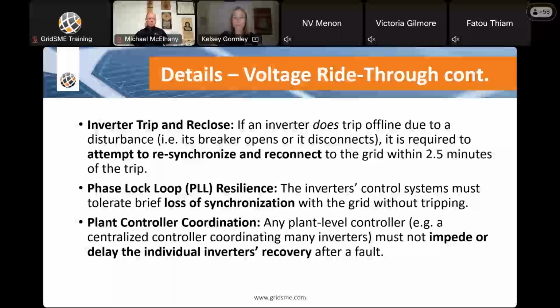Inverter control systems must tolerate a brief loss of synchronization with the grid without tripping. If the grid voltage phase reference is lost or slips, the inverter's PLL should freeze at the last known phase angle and continue injecting current at that phase for up to 150 milliseconds while the inverter attempts to relock to the grid. So they're not allowed to trip or stop output purely due to a short loss of sync. They have to ride through these events as well.